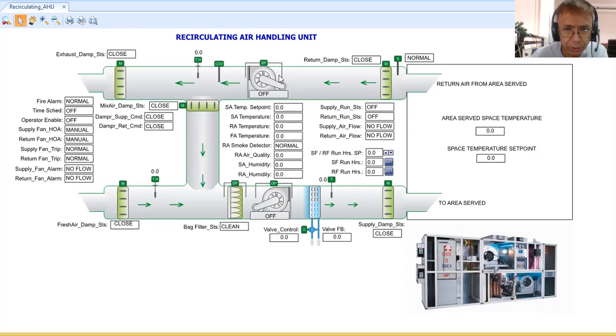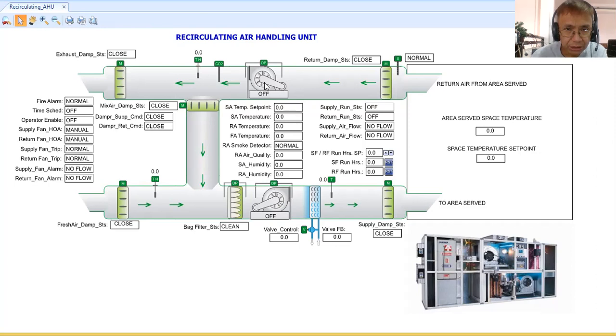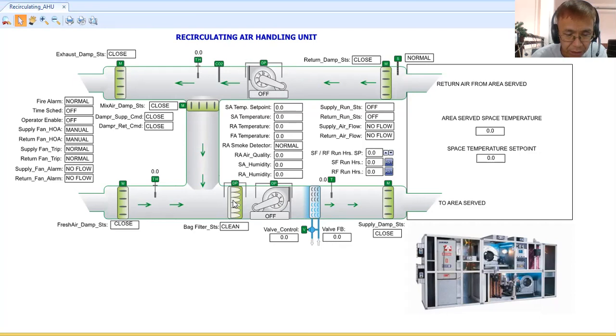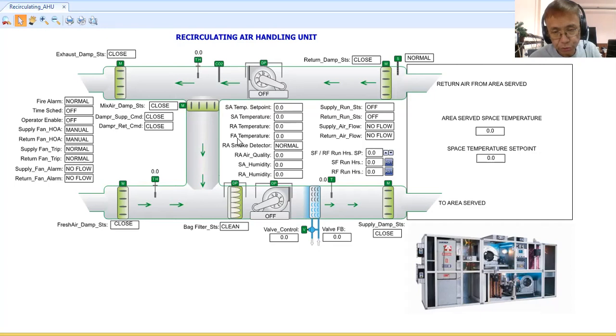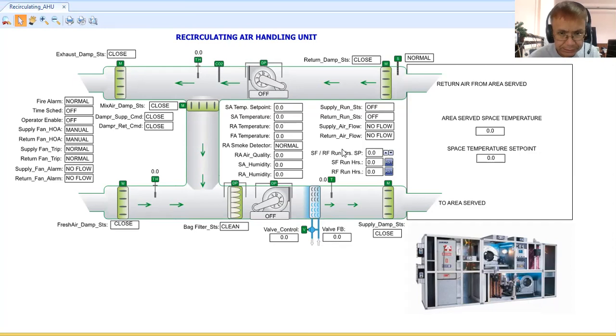There is a differential pressure switch across each fan to detect airflow and confirm the fan is working. I also have a differential pressure switch across the bag filter to monitor filter status. If the bag filter becomes clogged or dirty, pressure builds up and is sensed by the differential pressure switch. For details on how a differential air pressure switch works across a filter, refer to my previous video tutorial.